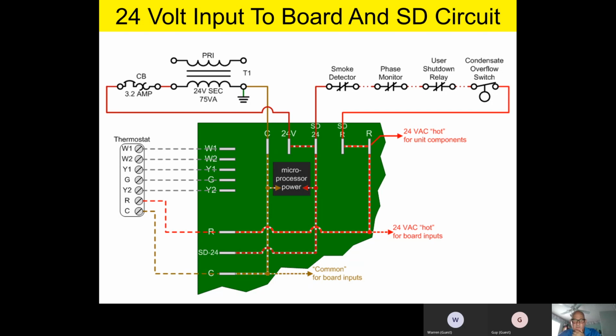Now, it should be noted, this is an important concept. Unlike our competitors, when they have a problem, say a smoke alarm or something like that, they shut all the 24 volts down and kill the microprocessor. We don't do that. What we do is keep the microprocessor alive, so to speak. So even if you have smoke detection, his little brain is still working. The microprocessor is powered all the time. Anytime you have power to the unit, you're going to have 24 volts on C and 24 V to power up the microprocessor.